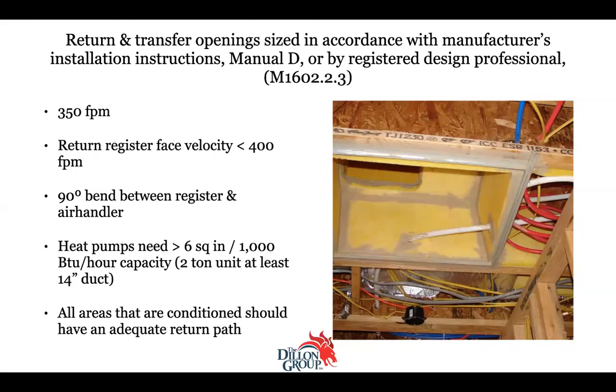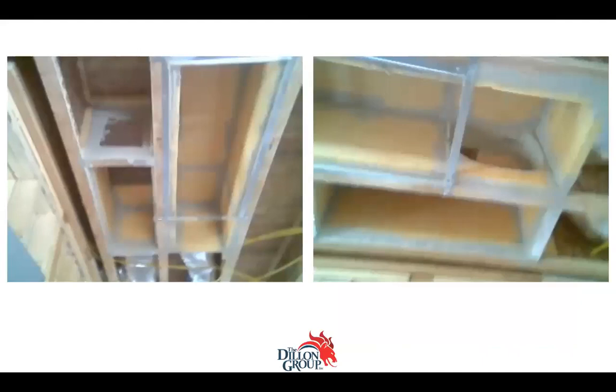And so in this case right here, we had a gigantic return grill. It was about 6 feet long. And I'm out there looking at it, and I'm going to the HVAC contractor. Your return is too small. So this is for a 4-ton unit. And this was the first floor system. They had a 4-ton unit on the first floor, and the air handler's up in the attic. I said, the return's too small.